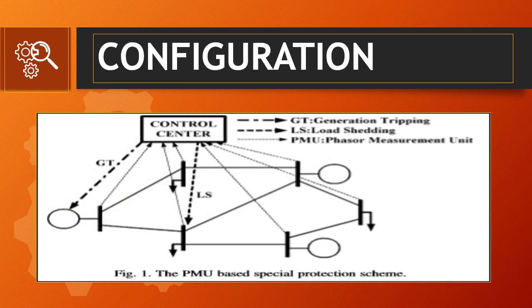This figure 1 is the PMU based special protection scheme, as shown on the screen. This figure shows that in the control center we use PMUs to monitor the generators and the major EHV transmission lines of a power system, and apply an instability prediction algorithm for initiating a SPS to avoid a sequence of related events whenever necessary. When a fault happens, we group the generators swinging coherently and reduce the system to one machine infinite bus system. Then using real-time phasor measurements to estimate the parameters of OMIB system.